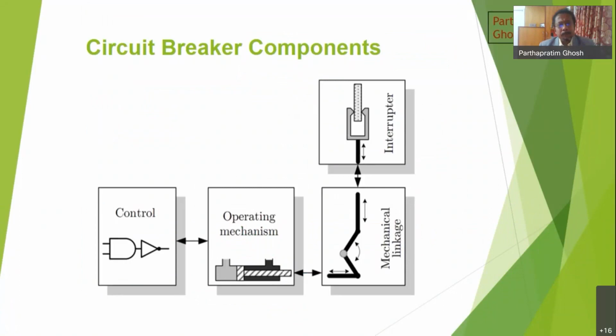There are four major building blocks of a circuit breaker. First is the controller, which controls the function of a circuit breaker. Then the operating mechanism, which is a mechanical device, and through a mechanical linkage it goes to the interrupter. That is the portion of the circuit breaker which interrupts the faulty currents. So these four major building blocks make a complete circuit breaker.